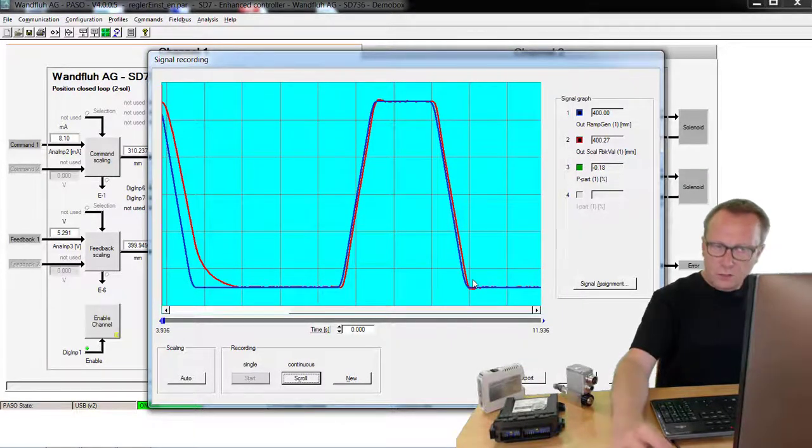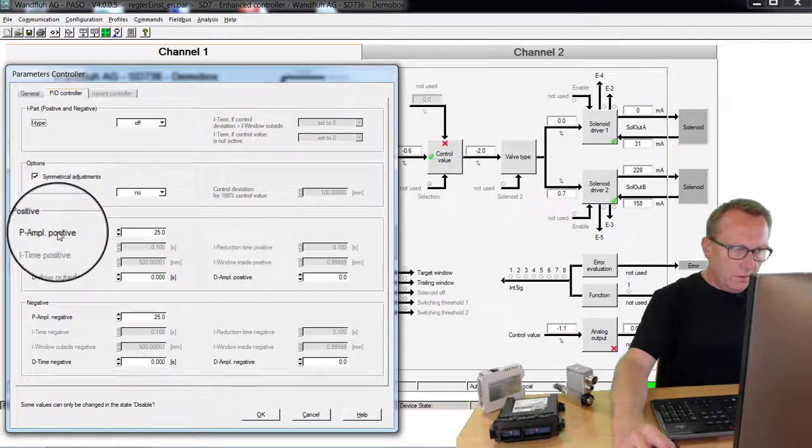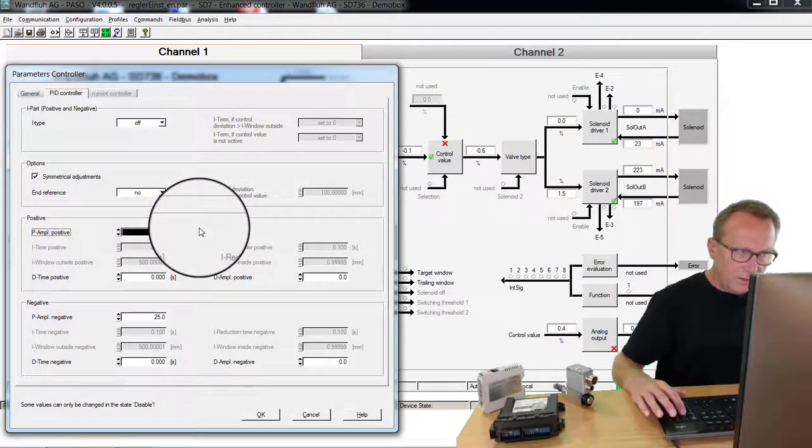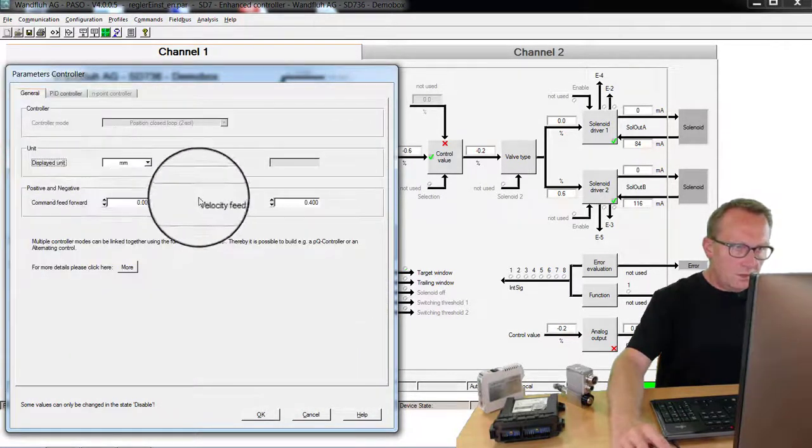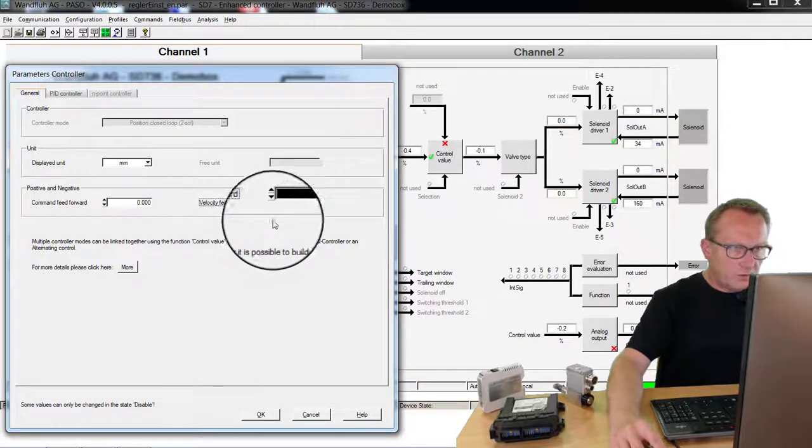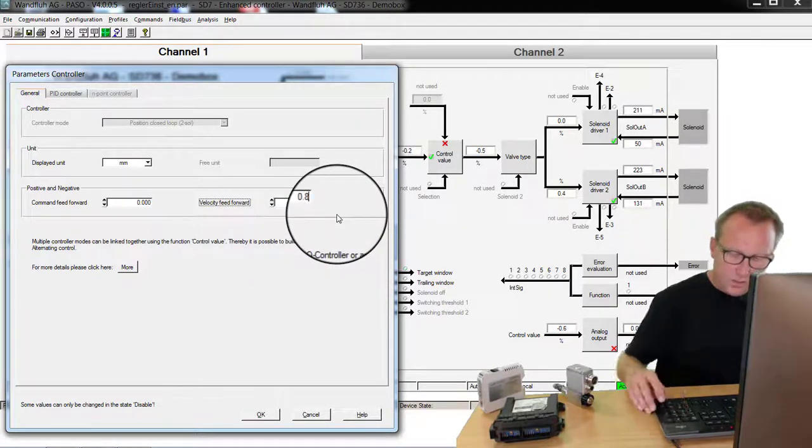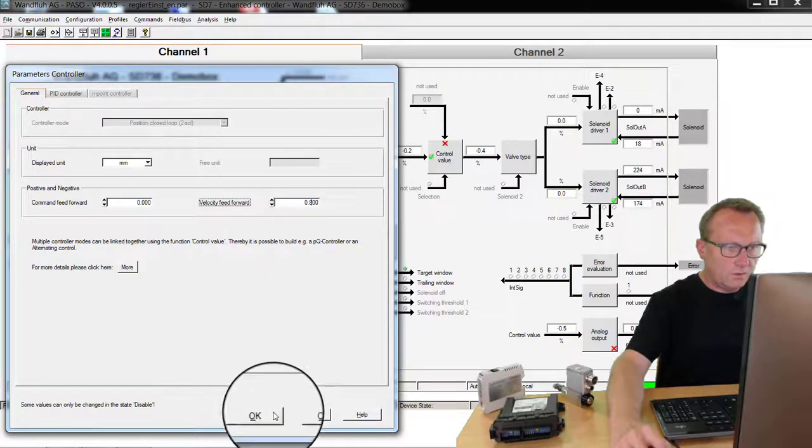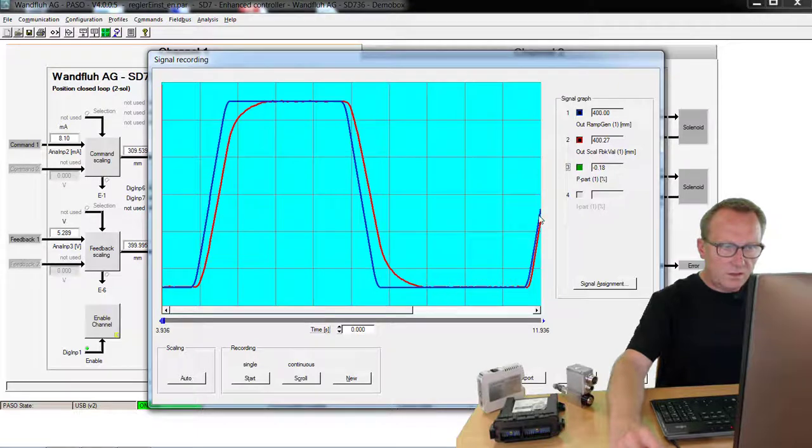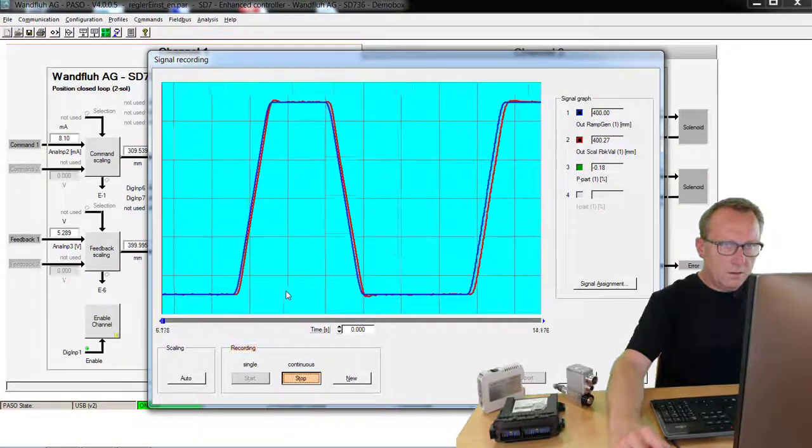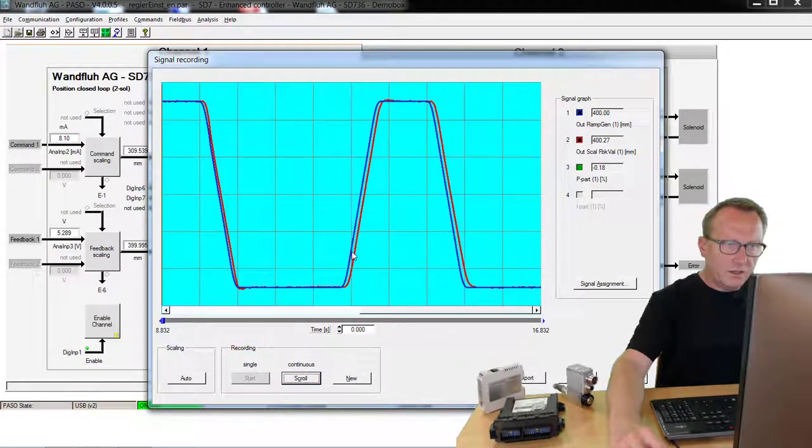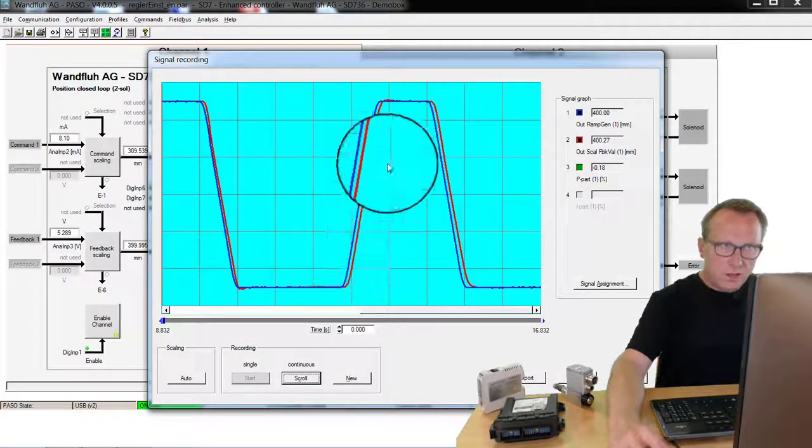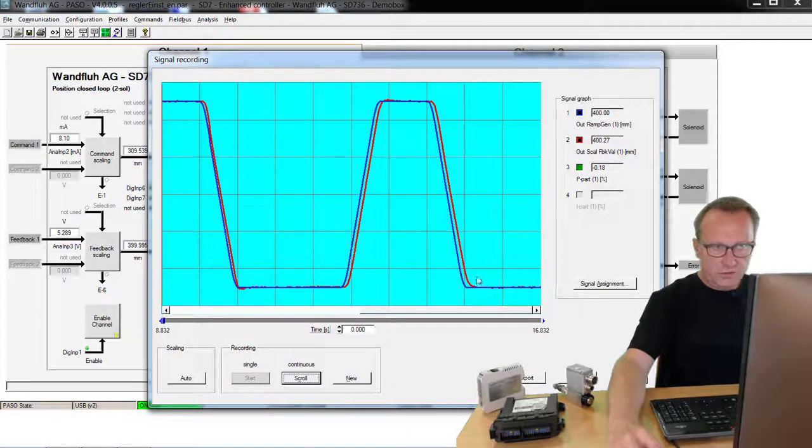If this is not allowed, we have to re-change the parameters. For example I decrease again the P amplification. For example to 8. But I accelerate the compensation of the control deviation with the parameter velocity feedforward. As an example 0.8. Go back to the signal recording. We will see what happens. Now you see we have a control deviation which is quite good. But we do not have an overshoot by moving into the position.